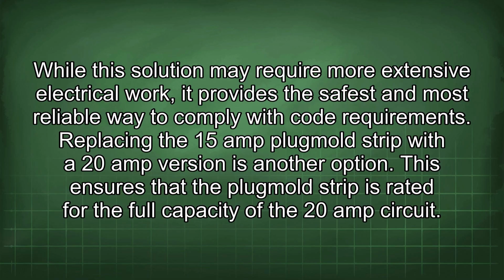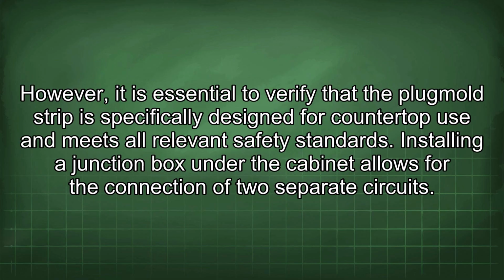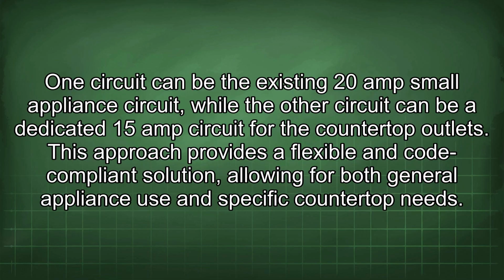This ensures that the Plugmold strip is rated for the full capacity of the 20 amp circuit. However, it is essential to verify that the Plugmold strip is specifically designed for countertop use and meets all relevant safety standards. Installing a junction box under the cabinet allows for the connection of two separate circuits. One circuit can be the existing 20 amp small appliance circuit, while the other circuit can be a dedicated 15 amp circuit for the countertop outlets. This approach provides a flexible and code-compliant solution, allowing for both general appliance use and specific countertop needs.